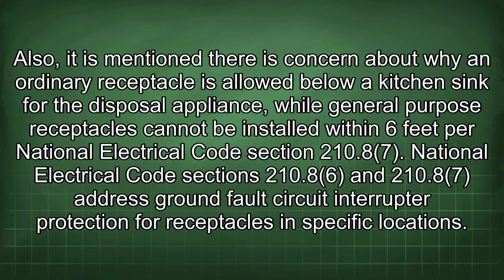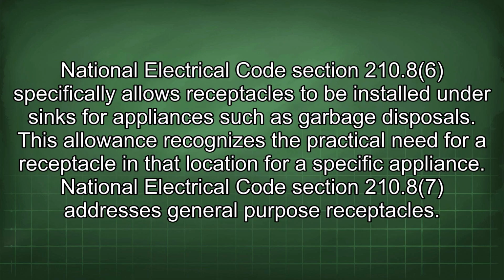Also, there is a concern about why an ordinary receptacle is allowed below a kitchen sink for the disposal appliance, while general-purpose receptacles cannot be installed within 6 feet, per National Electrical Code Section 210.8(7). National Electrical Code Sections 210.8(6) and 210.8(7) address ground fault circuit interrupter protection for receptacles in specific locations. Section 210.8(6) specifically allows receptacles to be installed under sinks for appliances such as garbage disposals. This allowance recognizes the practical need for a receptacle in that location for a specific appliance.